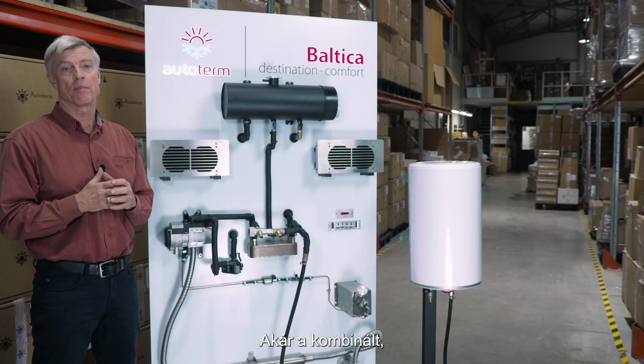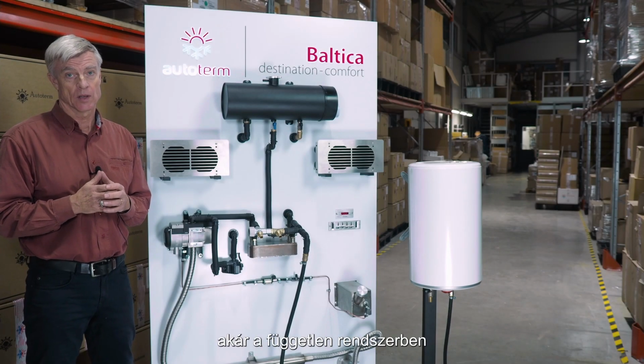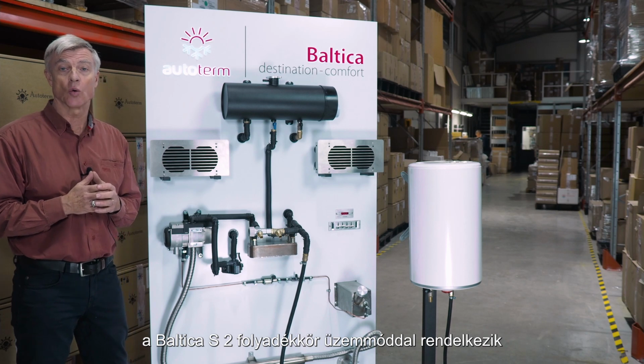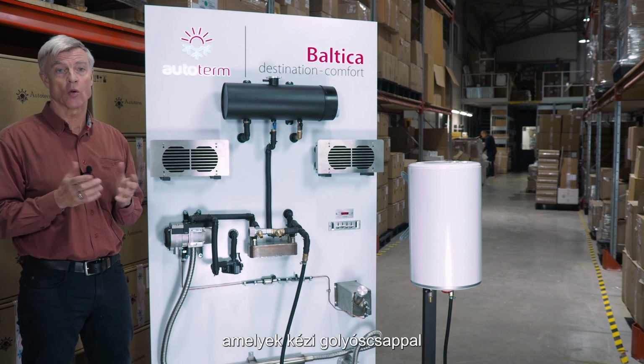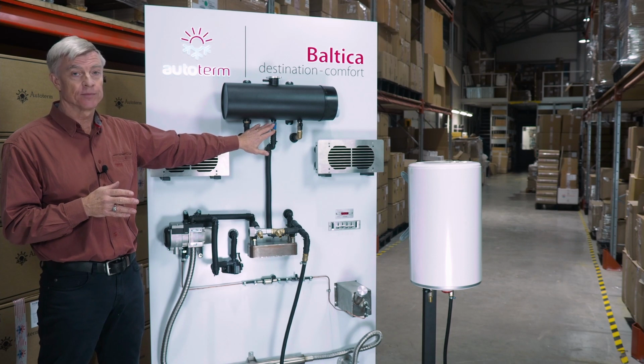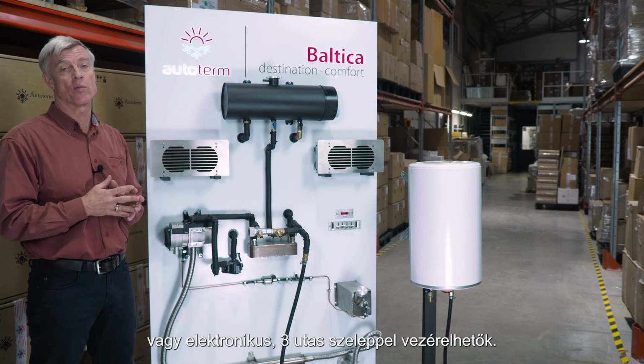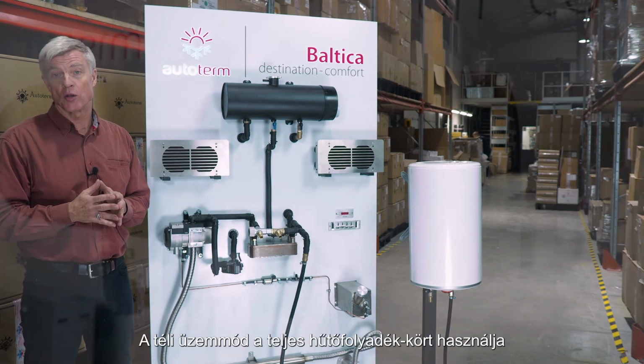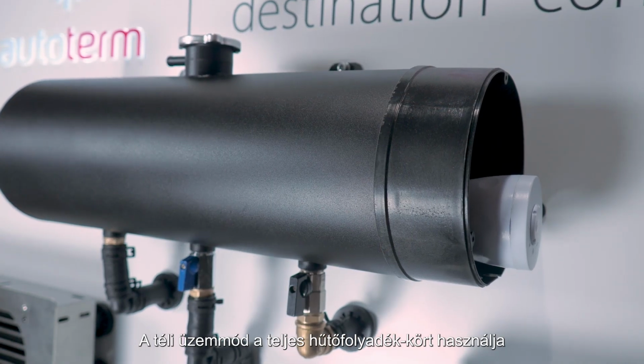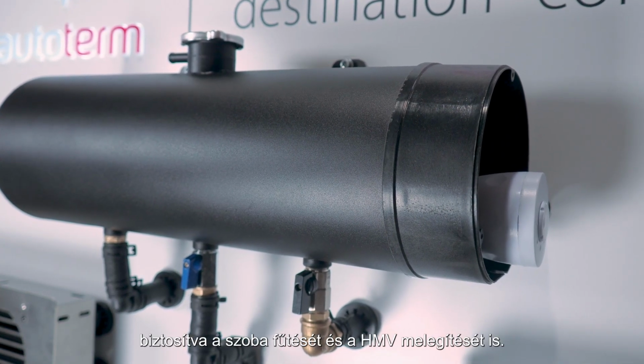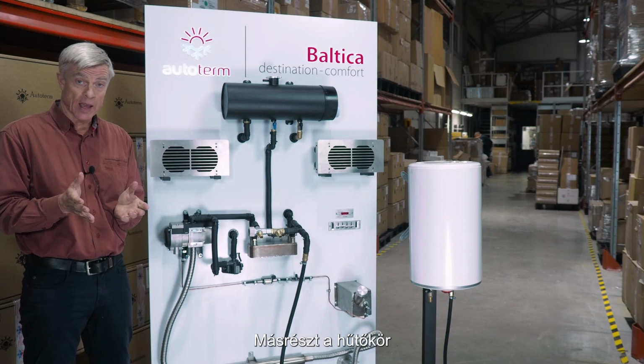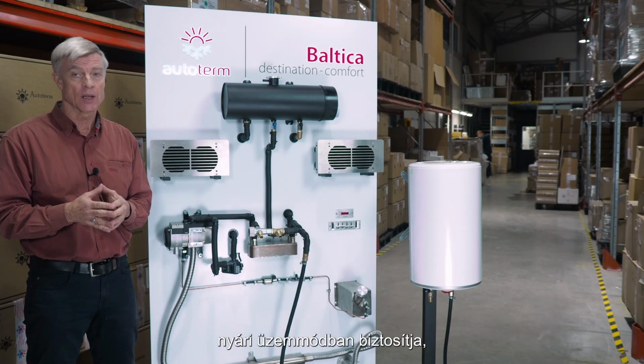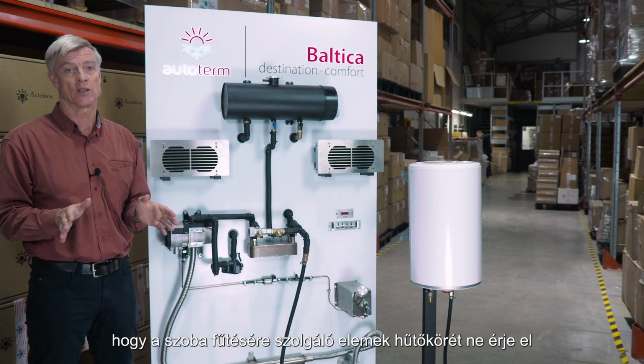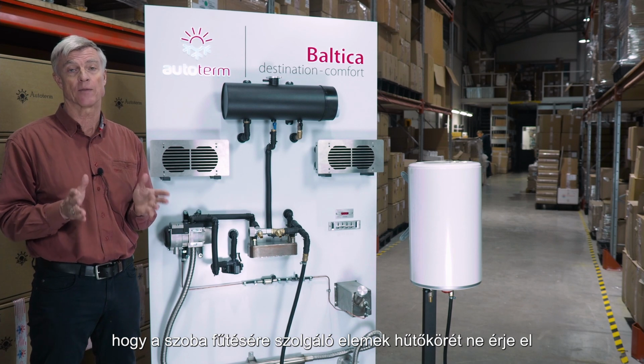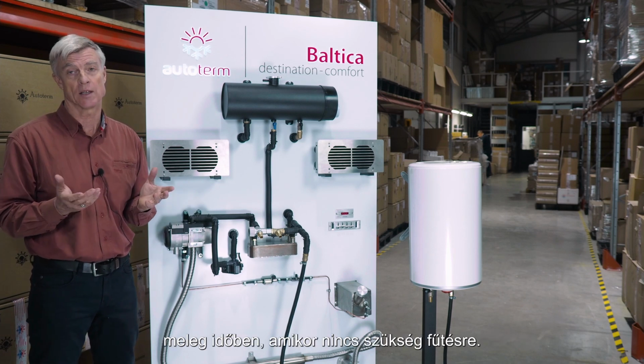In either the combined or the independent system, the Baltica S has two coolant loop modes that can be controlled by the manual ball valve or the electric three-way valve. The winter mode utilizes the full coolant loop, providing room heating and domestic water heating. On the other hand, the coolant loop summer mode ensures the coolant does not reach the coolant loop of components meant for room heating when not needed in the warm weather.